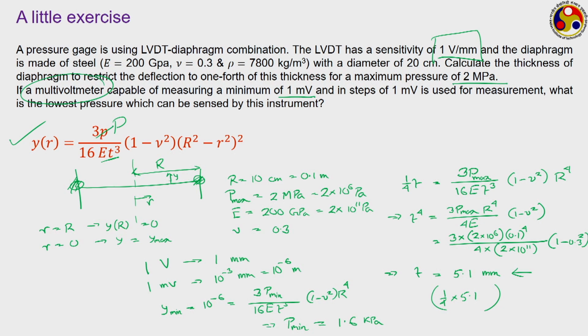Remember, this 1.6 kilopascal has nothing to do with the primary transducer. It has nothing to do with this diaphragm itself, rather it is related to the secondary transducer, or not even the secondary transducer, but how you are measuring the final output. If we can use a multi-voltmeter or any other voltage measuring instrument which can give you a minimum lower than this 1 millivolt, then we can go to an even lower value of this minimum pressure. So, this way we can calculate for any kind of elastic pressure transducers just by knowing the relation between the deflection and pressure, like the one shown in red here.